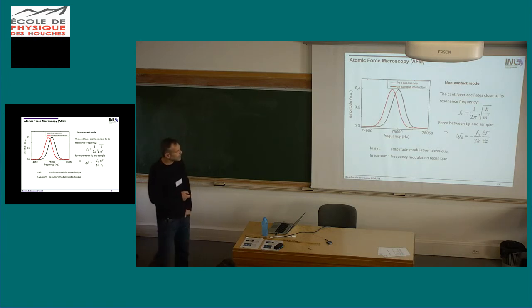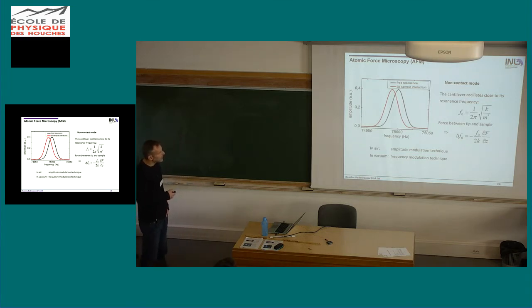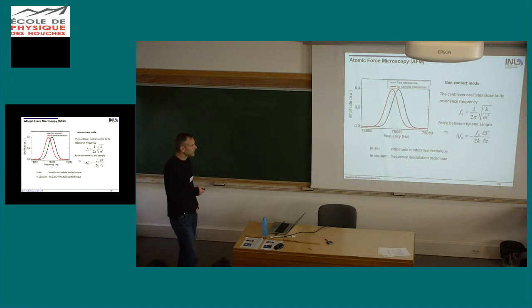And then there are two different ways to apply this. In air, normally you have an amplitude modulation technique. I will explain this in the next slides. And in vacuum, you cannot use this because your oscillation curve is very sharp. So what the amplitude modulation mode does is you excite, let's say, to one side of the resonance curve, and then as soon as your resonance curve shifts, your amplitude goes down if you excite there. So what you do then is you move back, you move closer, until you recuperate your amplitude. This is why it's called amplitude modulation.